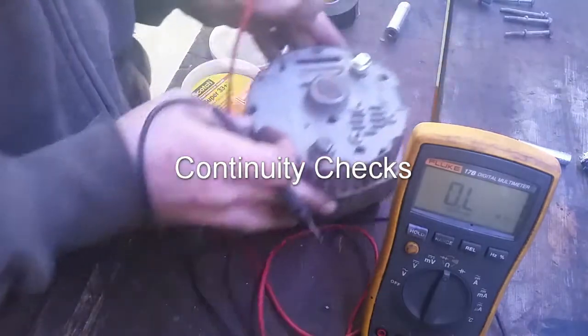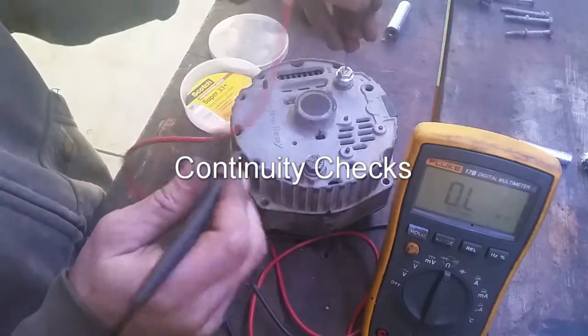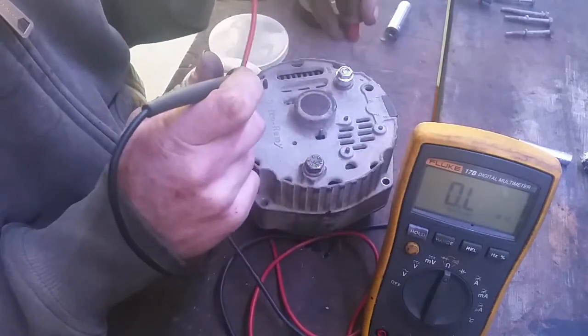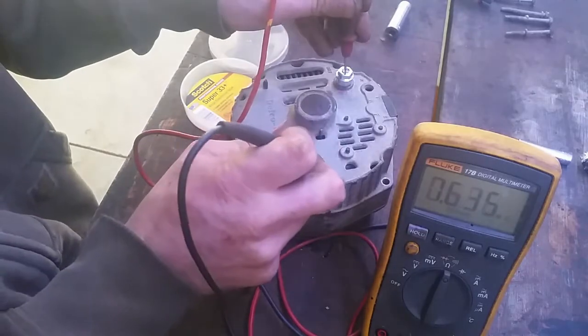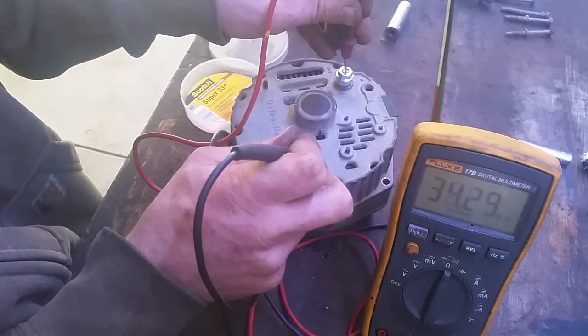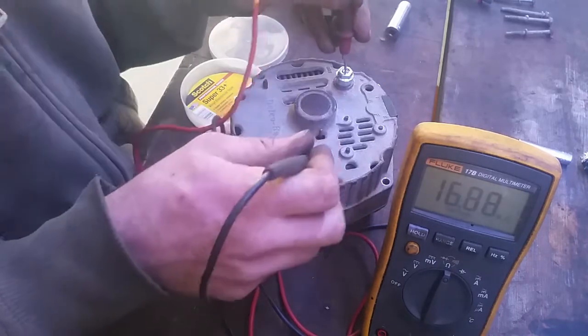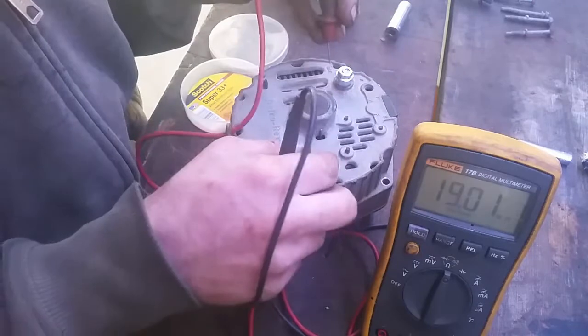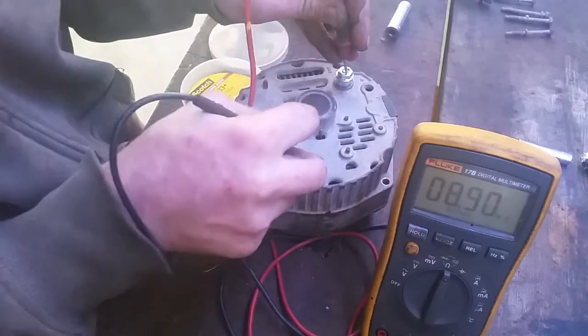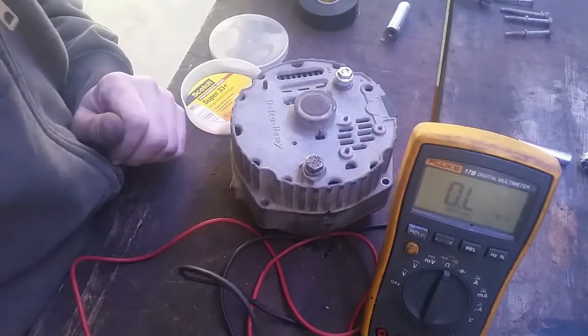Now that I got that replaced, I'm just going to check to make sure it's not grounded to anything. I'm going to take the meter and check continuity between the battery terminal and the grounding terminal. We're getting high meg — 16, 19 meg, whatever. So that verifies it's not shorted to the shell. And right to the shell: 8 meg. So we're good. Hopefully this works.